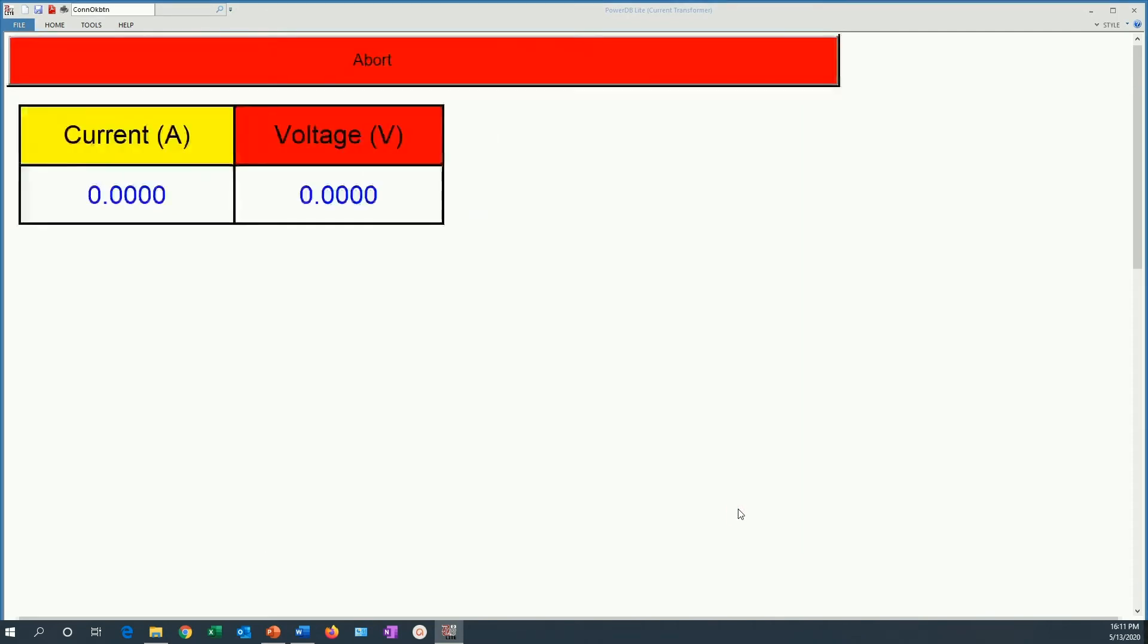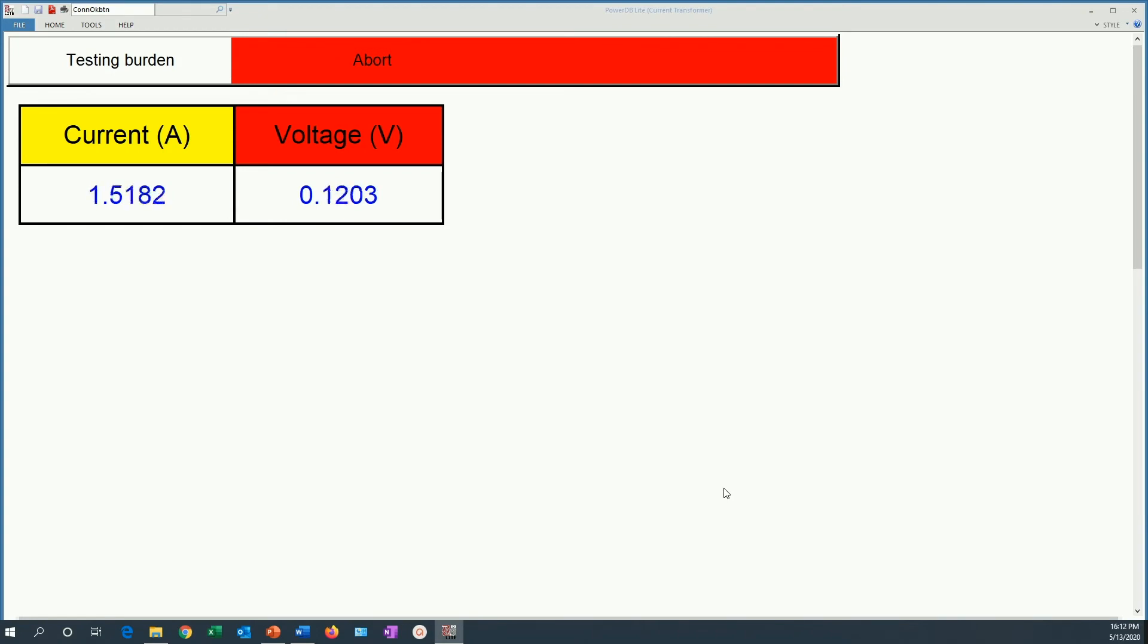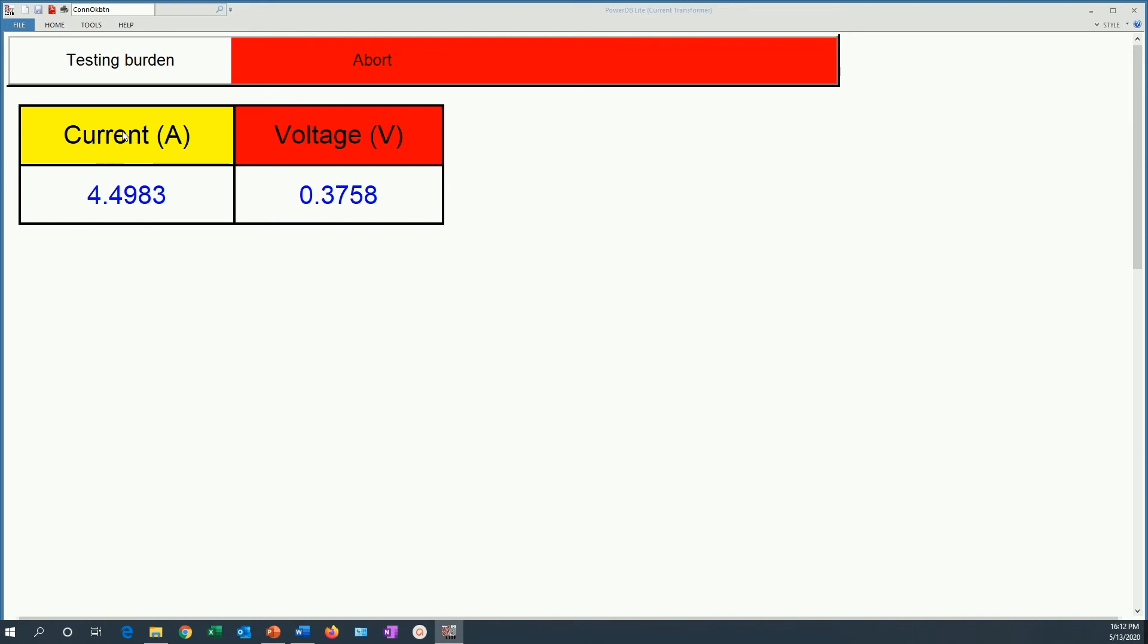And right now we are injecting 5 amps. We are actually performing a real life burden test on an electromechanical relay that I have connected here as an example. I am simply injecting 5 amps to the circuit of that single electromechanical relay. It is an over current relay. Now see how the current is ramping up. It is going to reach 5 amps.